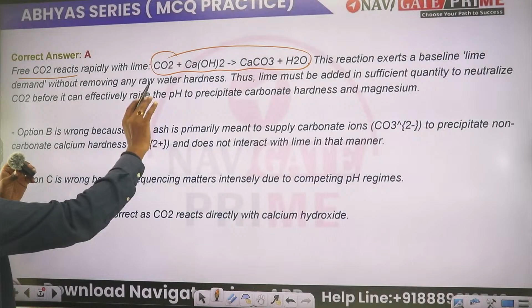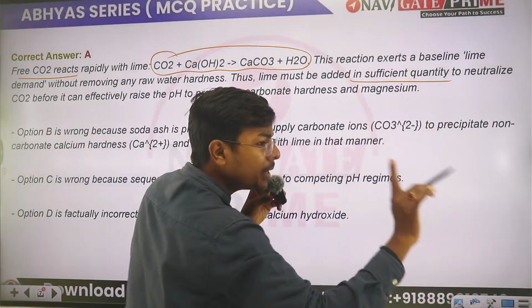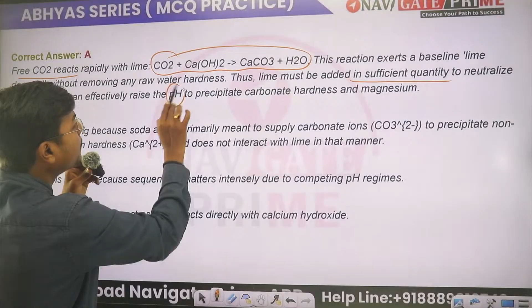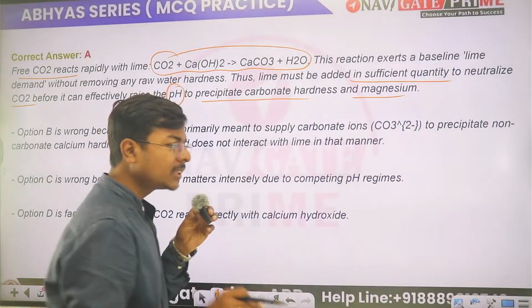Free CO2 reacts rapidly with lime. We know this reaction very well: CO2 and calcium hydroxide react and form calcium carbonate. The reaction exerts a baseline lime demand without removing any raw water hardness. Thus, lime must be added in sufficient quantity to neutralize the CO2 before it effectively raises the pH to precipitate the carbonate hardness. This concept should be very much clear in your mind.